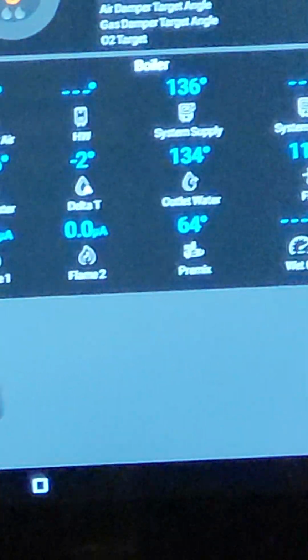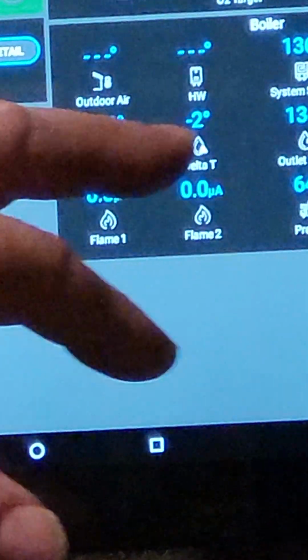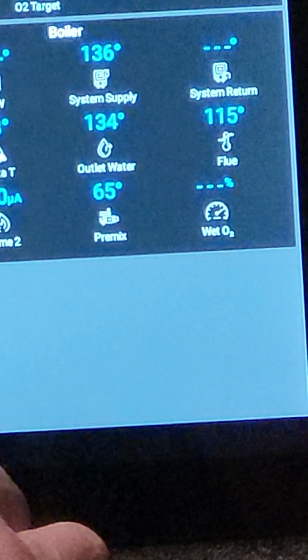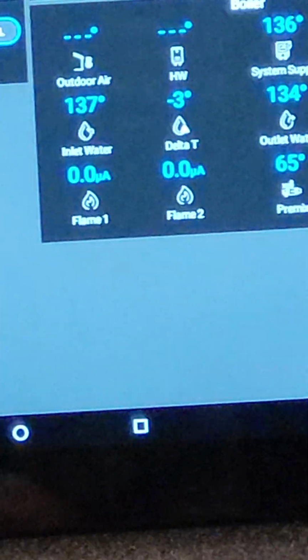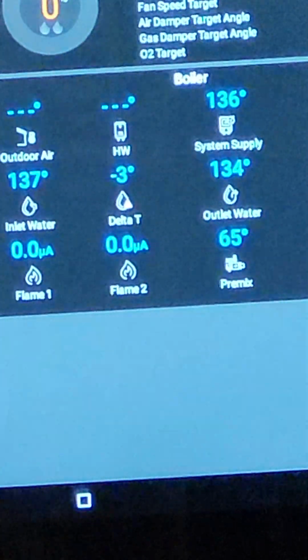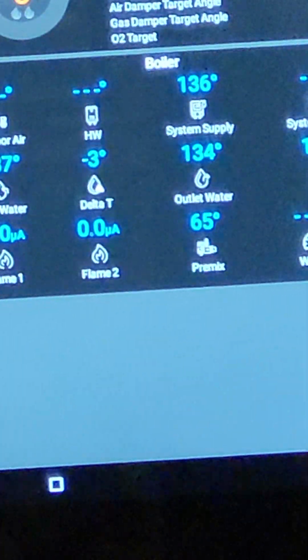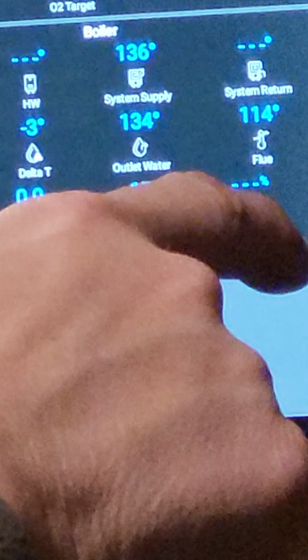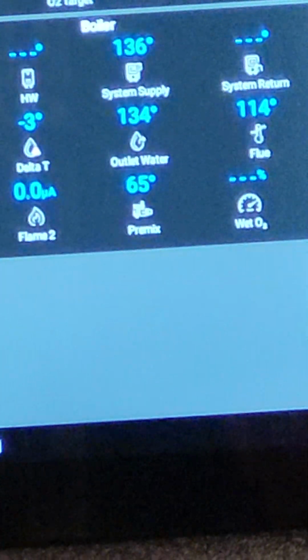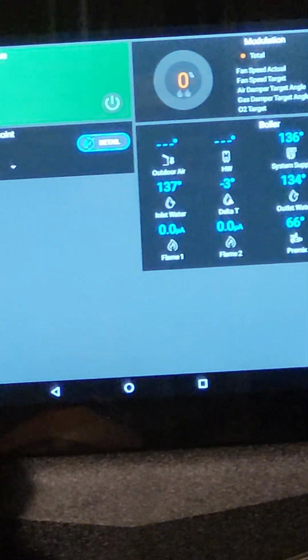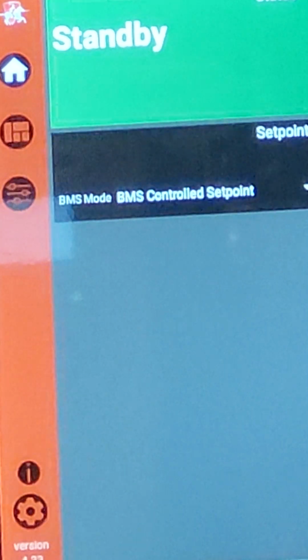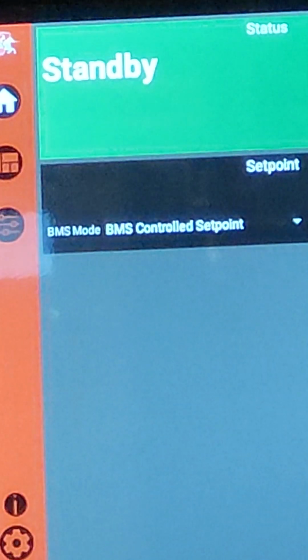Inlet water temperature, our delta T across the heat exchanger, our outlet water, our flue temperature, flame signal 1, flame signal 2, because we have 2 flame sensors in there. Our premix temperature, that's the temperature of the air in the unit right now, and then our O2. So right here underneath set point, it says BMS mode, BMS controlled set point. That means the building management system is controlling the set point of the boiler.